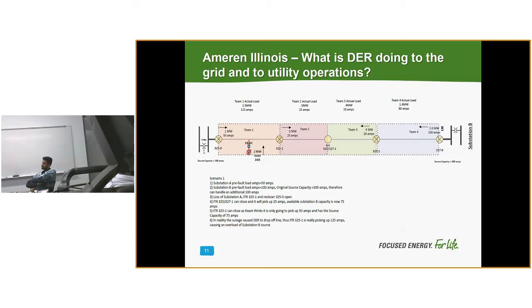So if I have an outage on this section here, where team 1 exists, the idea is I should be able to restore team 2 from the adjacent substation. This is a normal open point between the two circuits. If I lose this section, 325-1 will open, 325-0 will open, isolating that problem. Then we will check to see if substation B can pick up the load on this section, and if it can, that normal open will close automatically. All this happens, of course, in seconds, but that's the logic behind it. Does this make sense? Just want to make sure we're on the same page.